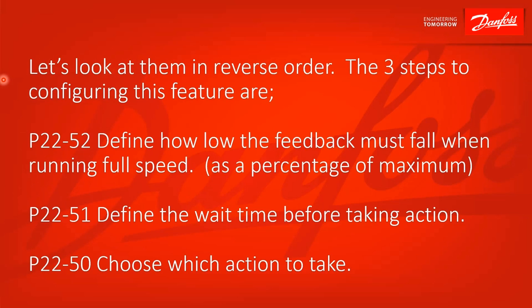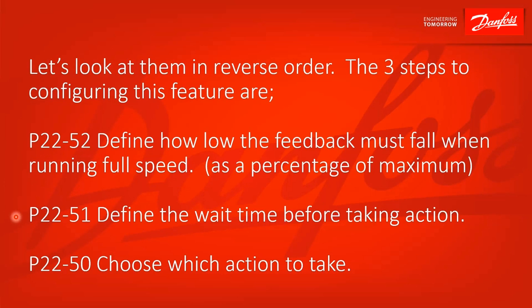Let's look at them in reverse order. This would be the three steps to configuring this feature. First, parameter 22-52, define how low the feedback signal must fall when running at full speed, and this is a percentage of maximum speed. 22-51, define the wait time before taking action. How long do you want it to be at full speed and that much below set point? And then 22-50, choose from a list of actions to take.